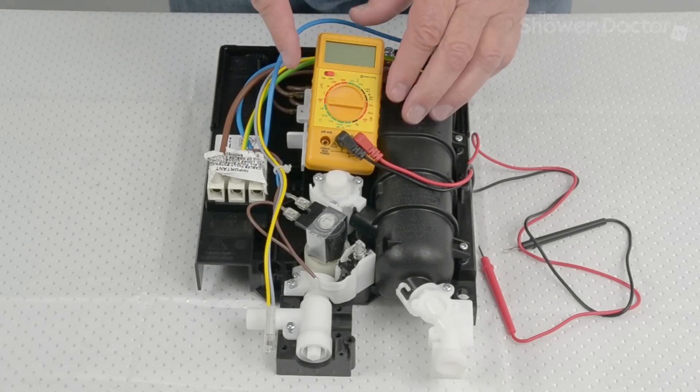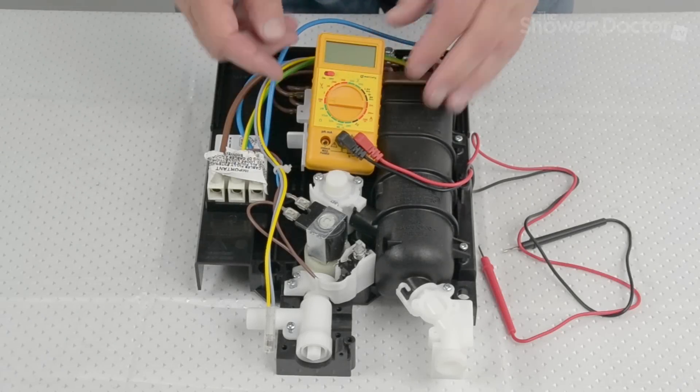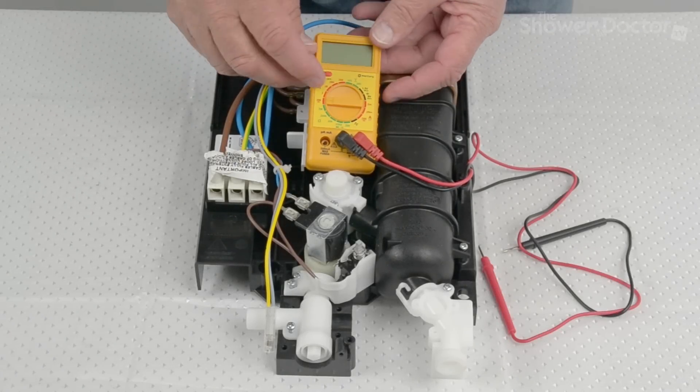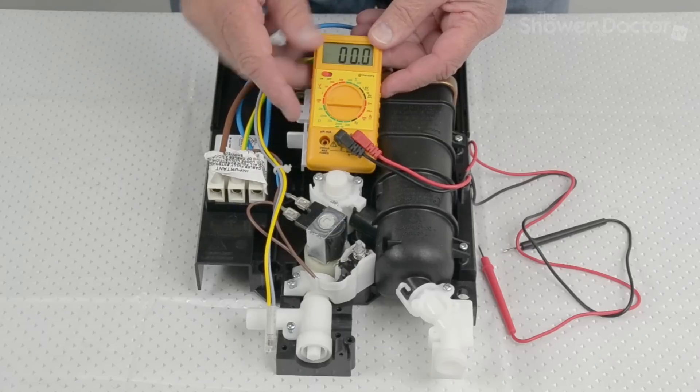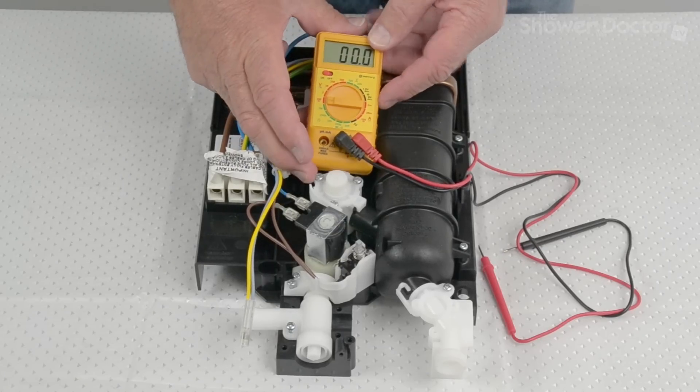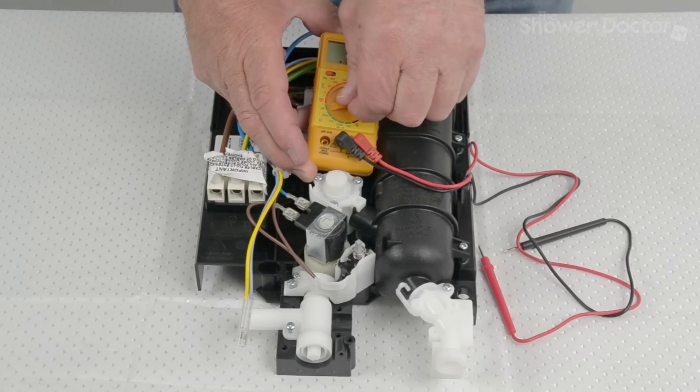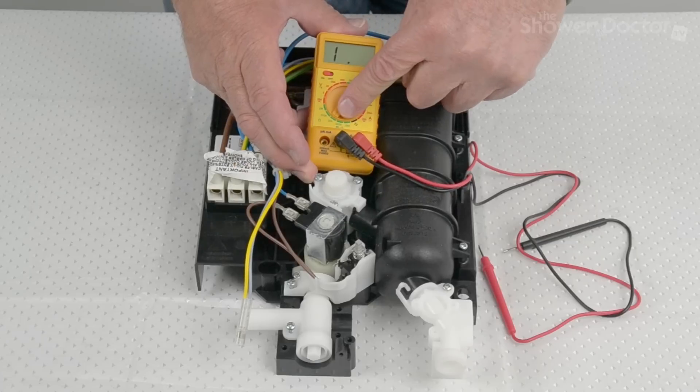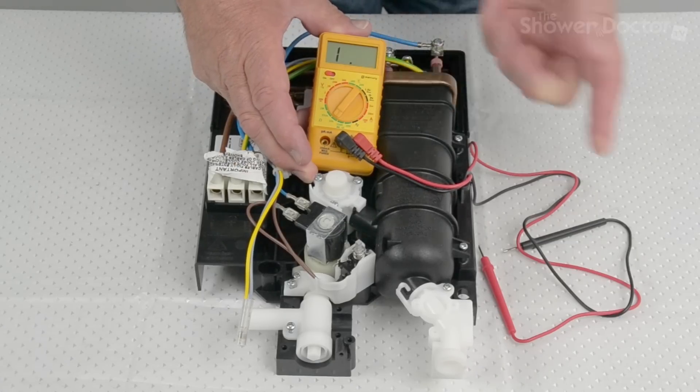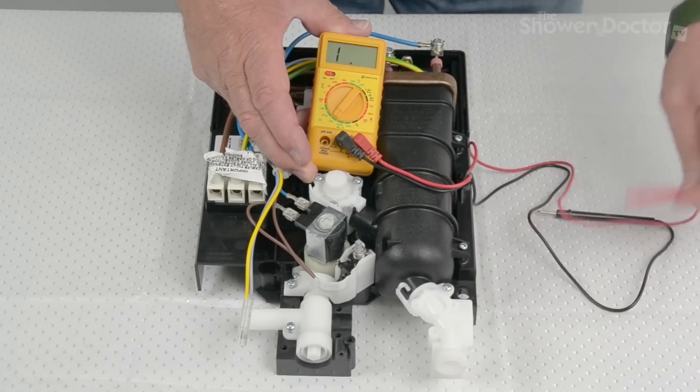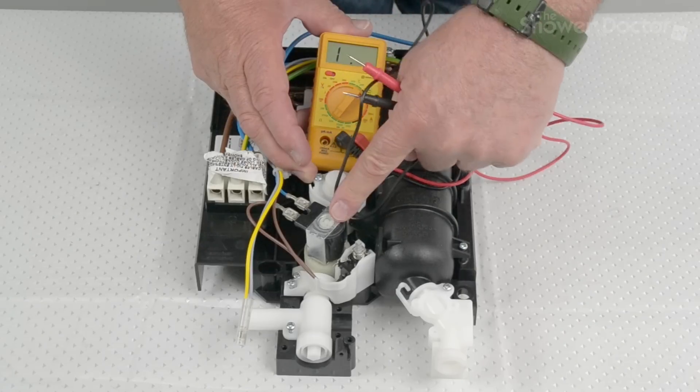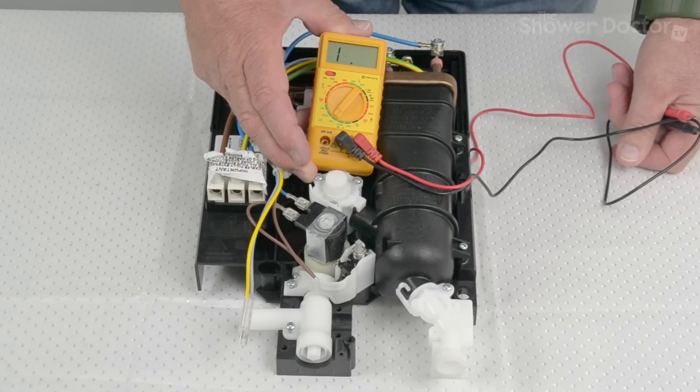Here we're going to use the multimeter to check a solenoid valve. So just to set the multimeter up, turn it on first. And then we need to set it on our multimeter to 20k ohms, which is down here. And what we're doing is measuring the resistance across the coil in the solenoid valve.